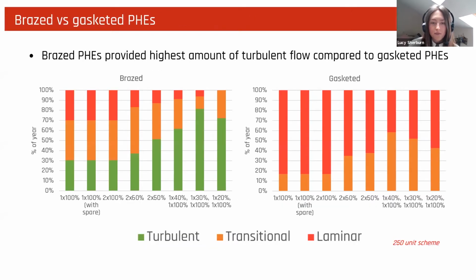Next slide, please. Initially, I investigated brazed and gasketed plate heat exchangers. They're the 2 types we typically see in this industry. I looked to compare their flow regime across the yearly load profile. Going back to the theory a little bit, your ability to transfer heat effectively depends on the turbulence of the medium, so high turbulence is really desirable. Laminar flow, at the opposite end, where you have low flow rates through your plate heat exchanger, gives poor performance. Your velocities are reduced. This can result in scaling and fouling on your plate heat exchanger. It can also increase the pressure drop across your unit. So this has a knock-on effect in terms of maintenance, lifespan, and your ability to transfer heat effectively.